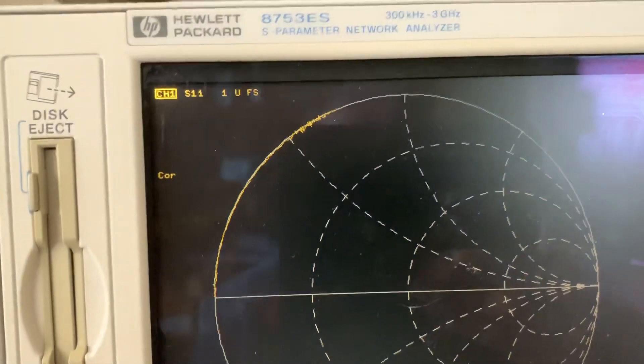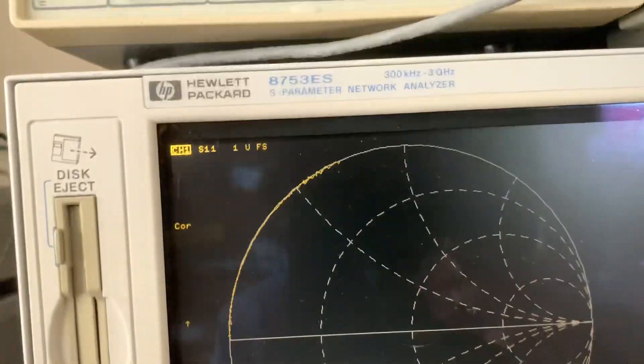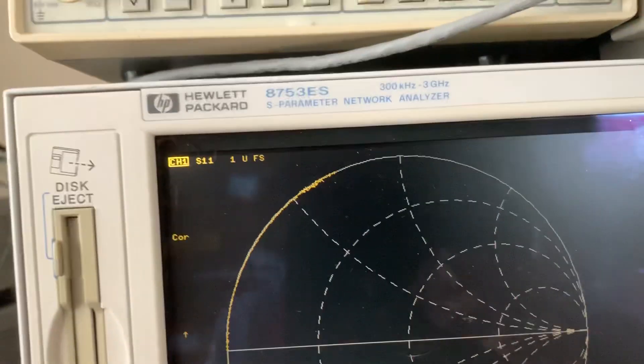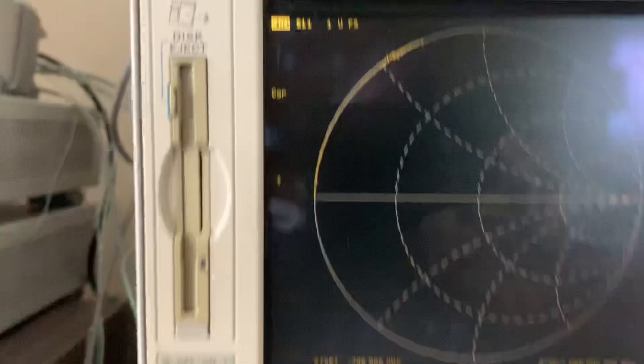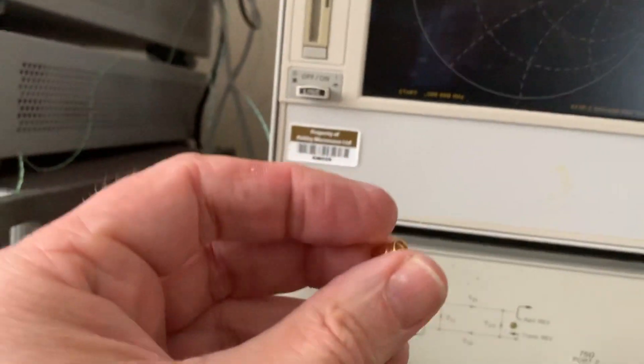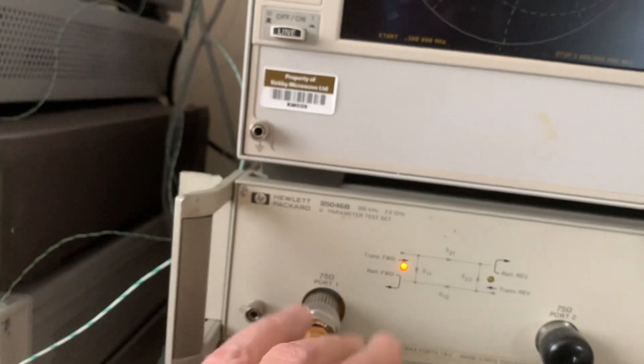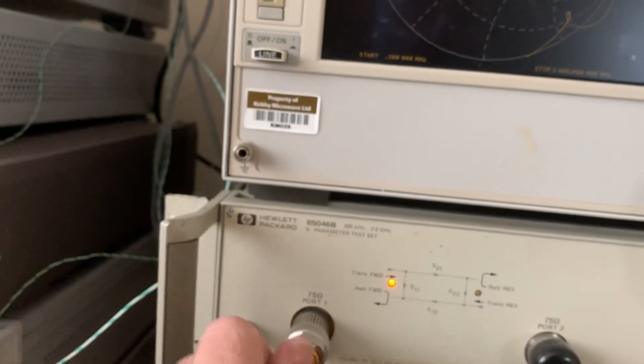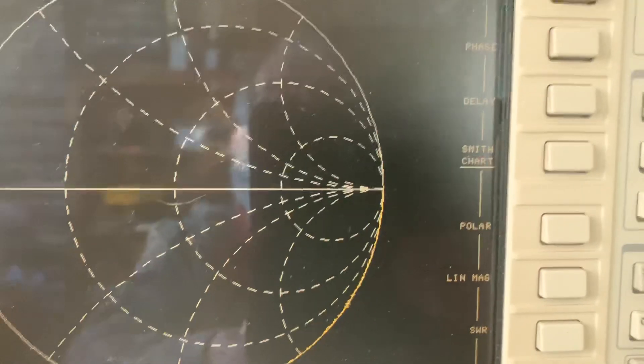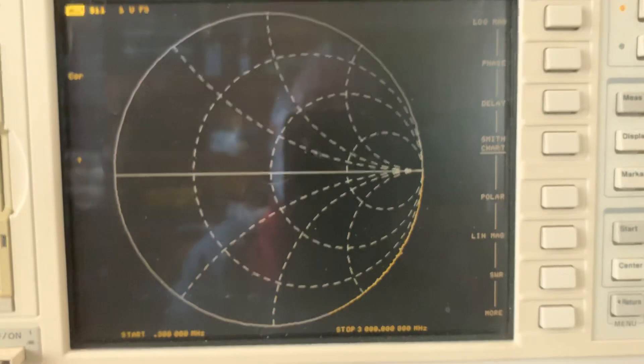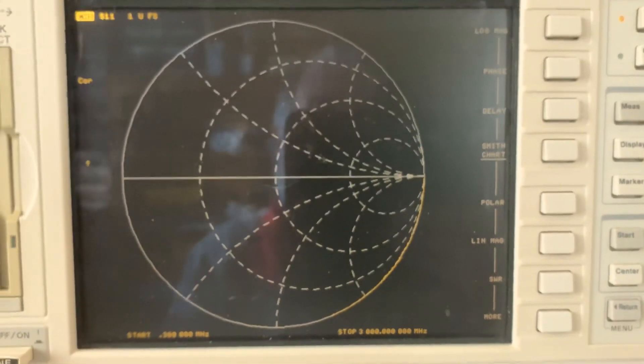Even though we've got an open, it looks like a perfect short. Now if we take the short, since when we calibrated we said it was an open, it will behave like an open.